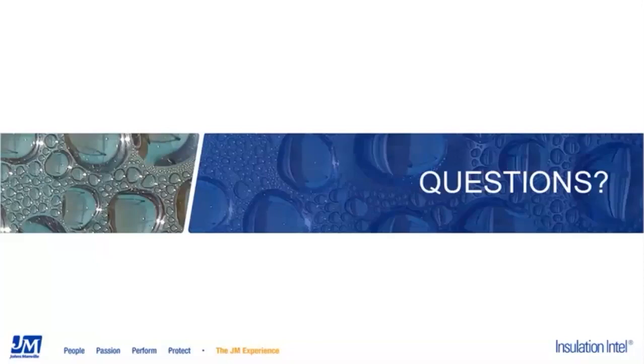There are tools that are used. 3E Plus was mentioned. JM also has internal calculators that work better for the Trymer and phenolic materials to determine the required thickness based on all those factors, including pipe size, which I didn't mention. All those factors together and some others I didn't mention go into the calculations. I won't get into the details here, but JM would be happy to work with anybody who had questions about pipe sizes. We can create pipe thickness tables or create thickness recommendations for your specific application.